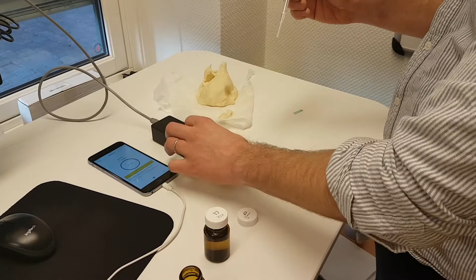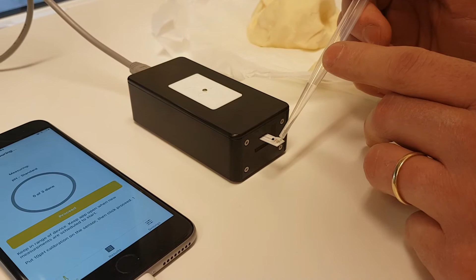So we have here 2 calibration solutions that ship with the box. This is the pH 10. So we're just going to suck up a little, it's around 30 to 50 microliters. It doesn't matter too much as long as we cover the full area of the sensor like this. There we go. So that's the pH 10, and then we can hit proceed on the app. And now it's going to take somewhere around 60 seconds for it to perform the first step in the two-step calibration.